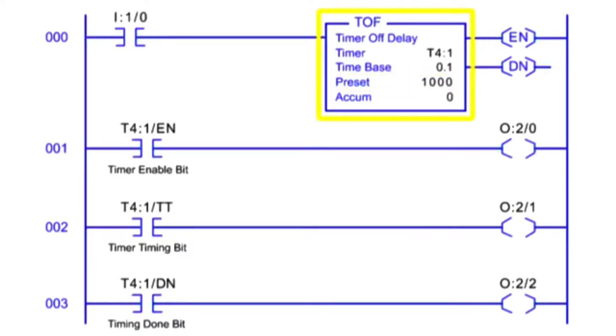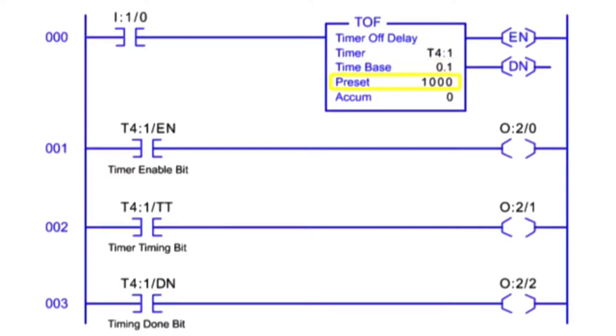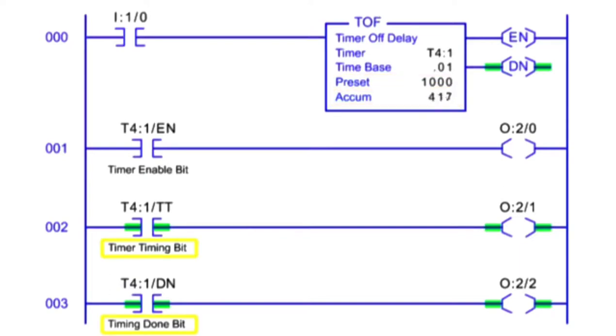The Timer Off Delay instruction is used to turn an output on or off after the timer has been off for the preset time interval. Similar to the Timer On Delay, the Timer Off Delay uses the same control bits, time base, and preset functions. The Timer Off Delay sets the Enable and Done bits when input conditions are true. When the input conditions change to false, the Timer Timing Bit goes true. As the accumulated value reaches the preset value, the Done and Timer Timing bits turn off.